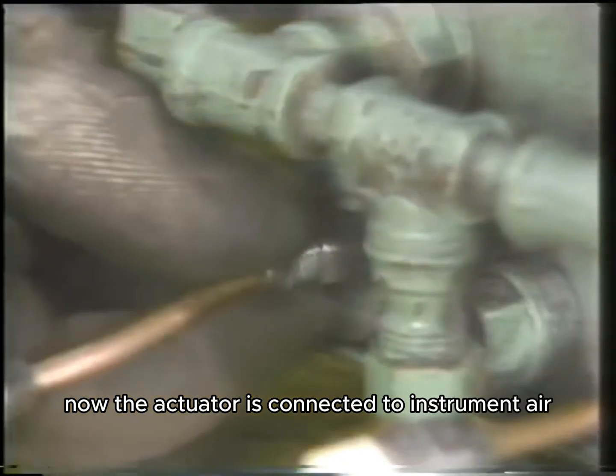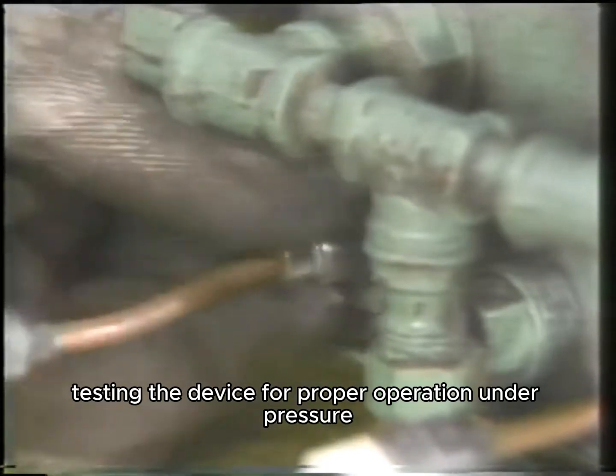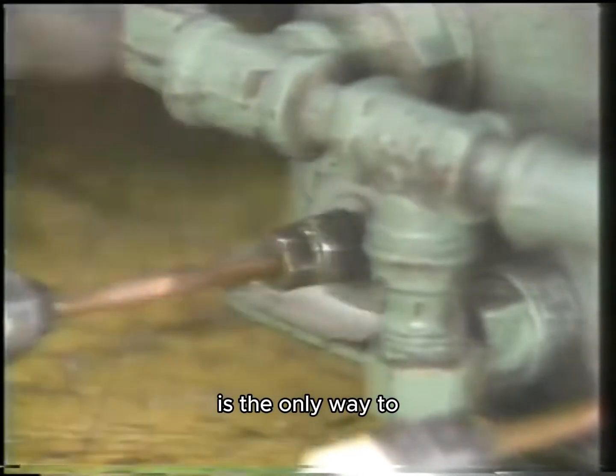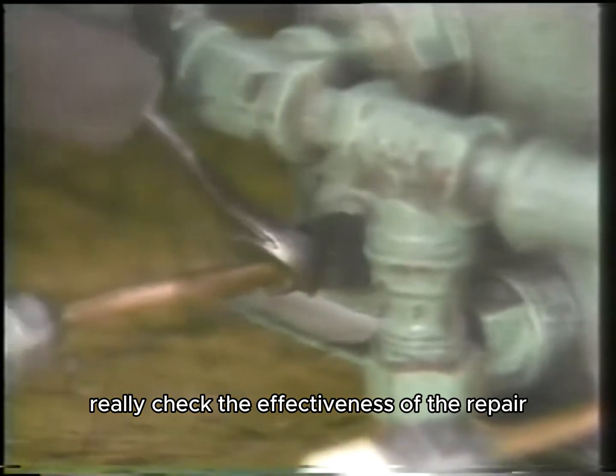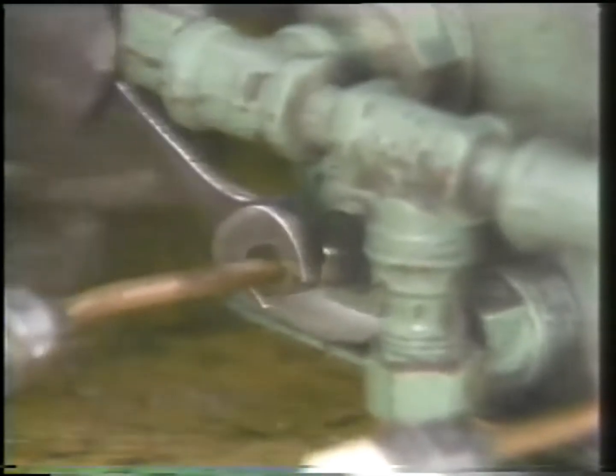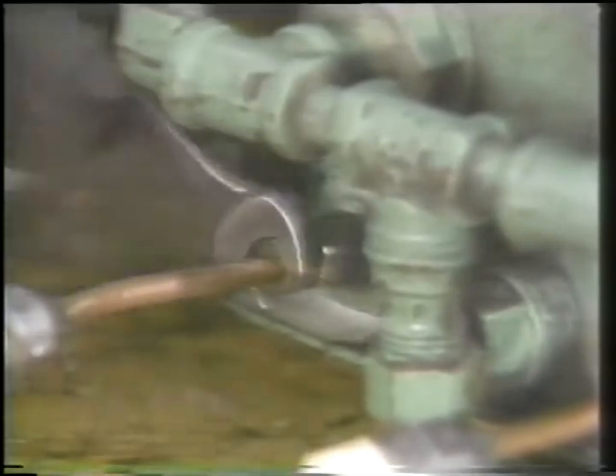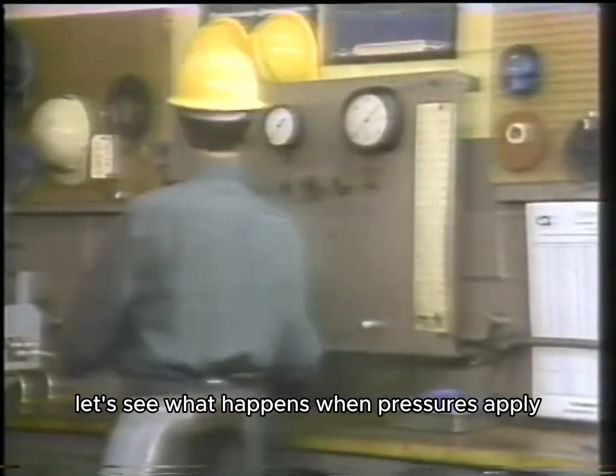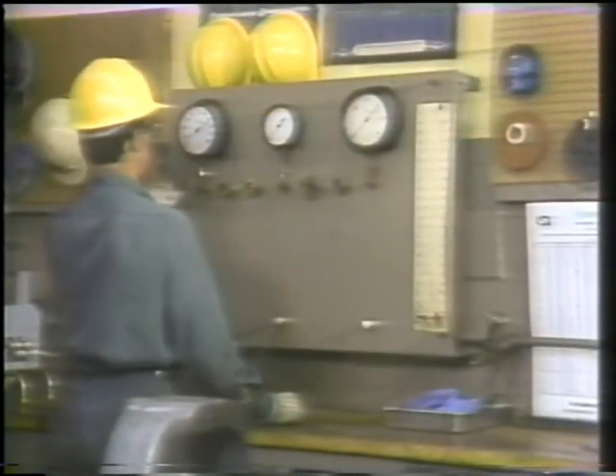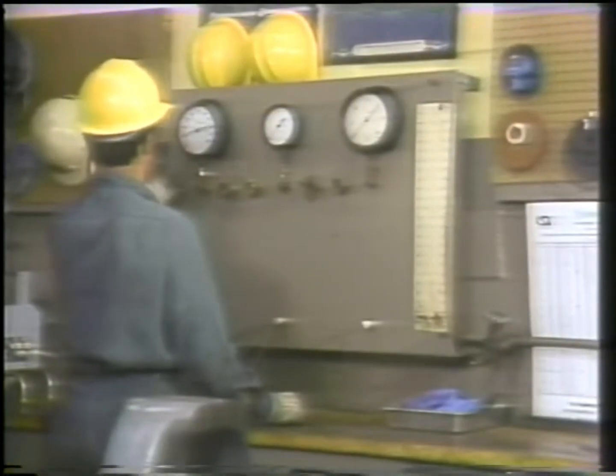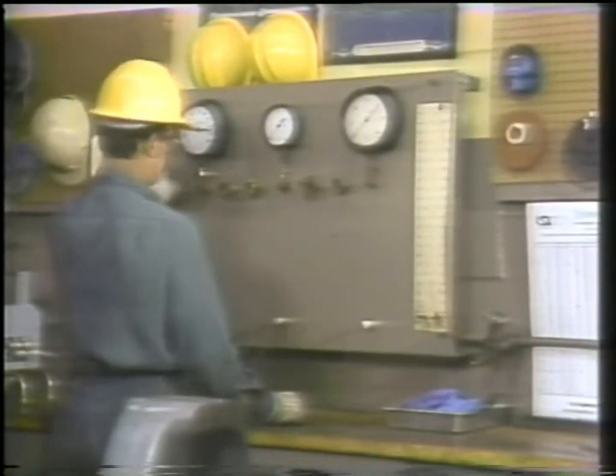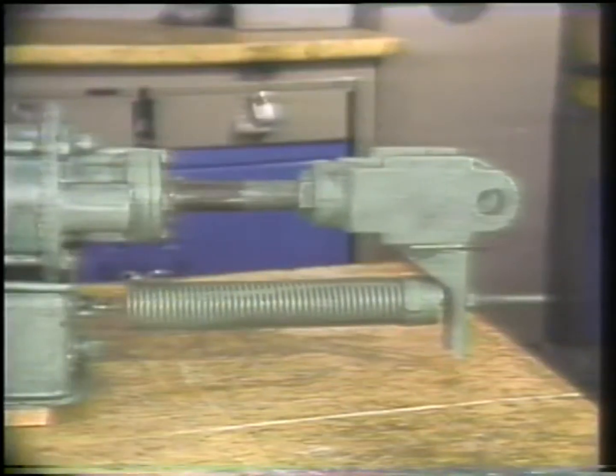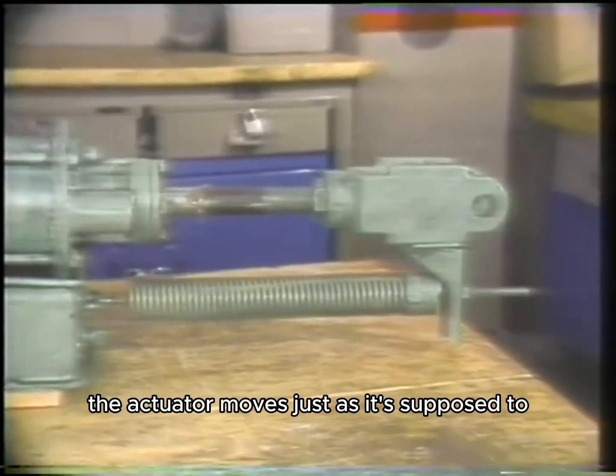Now the actuator is connected to instrument air. Testing the device for proper operation under pressure is the only way to really check the effectiveness of the repair. Let's see what happens when pressure is applied. The actuator moves, just as it's supposed to.